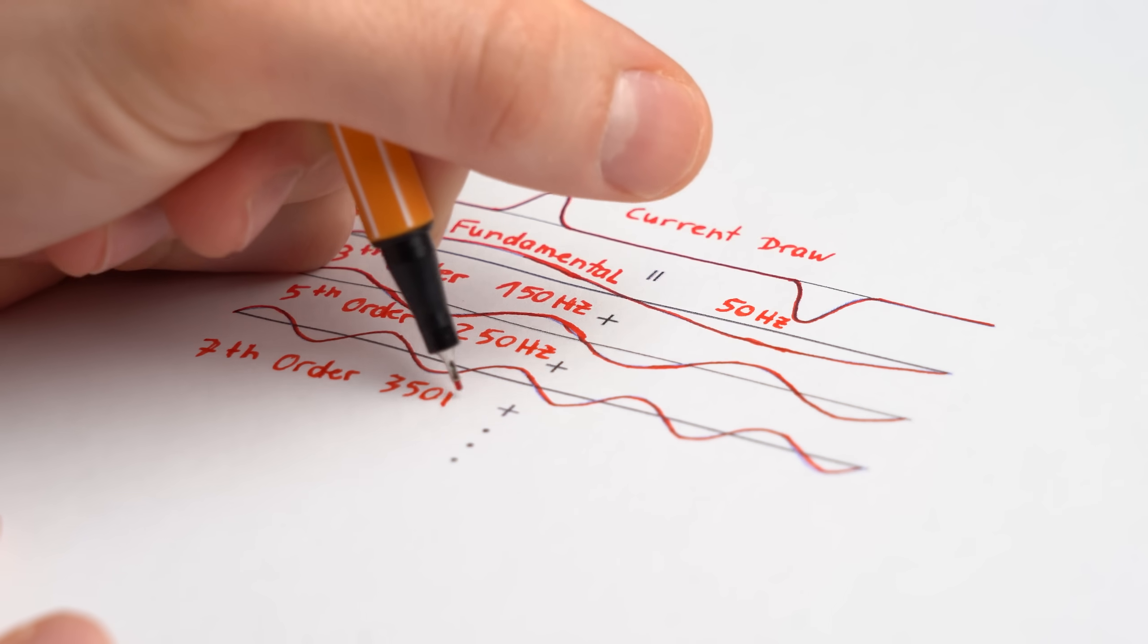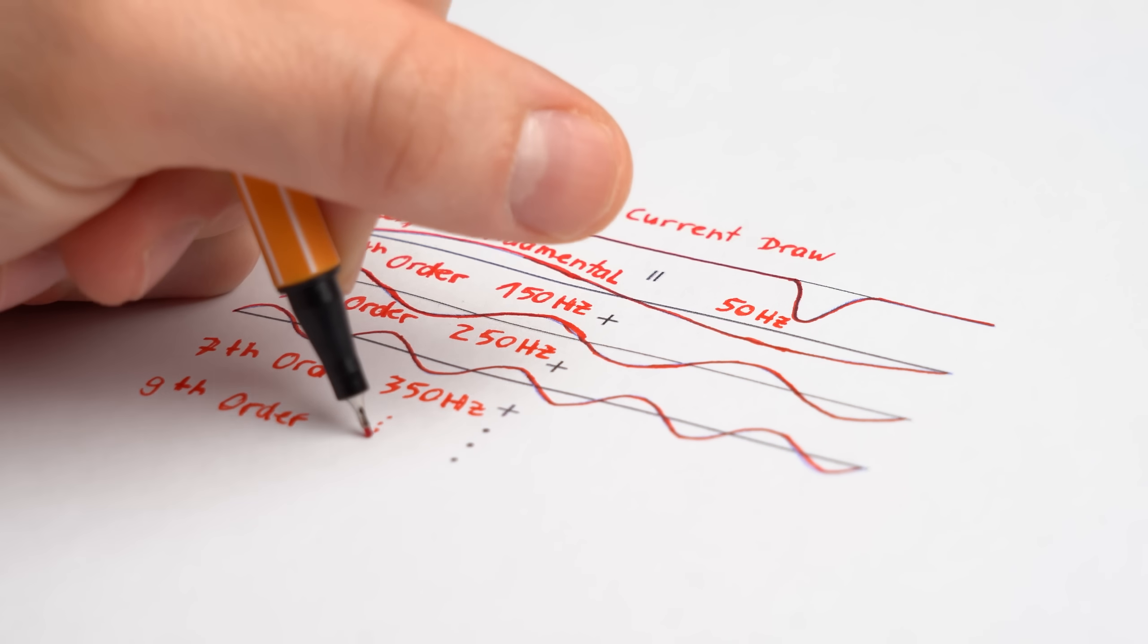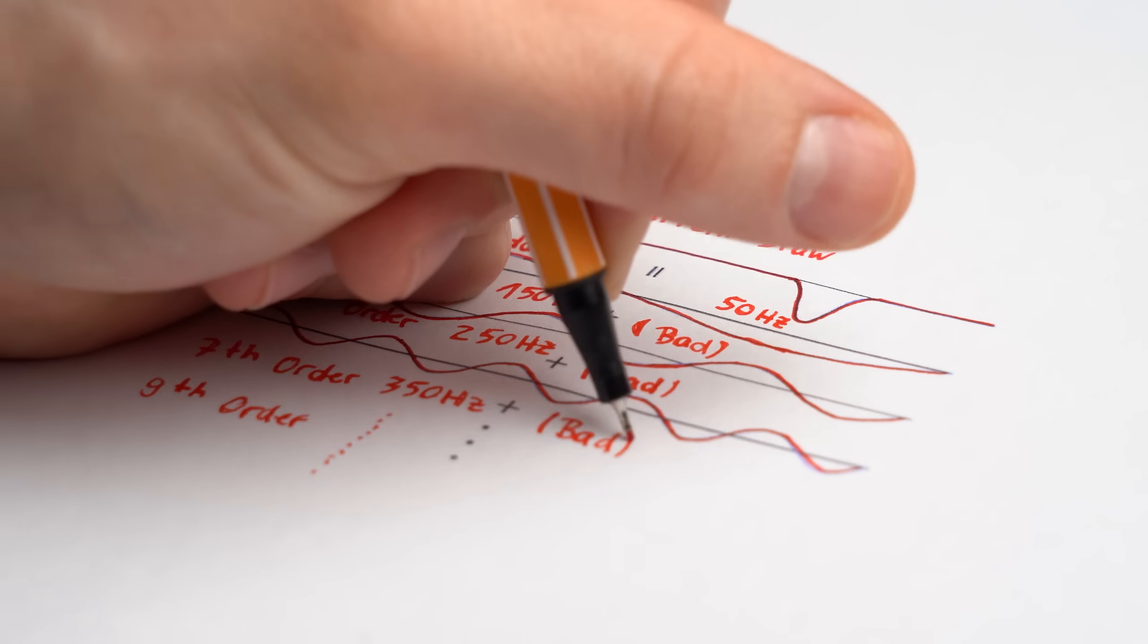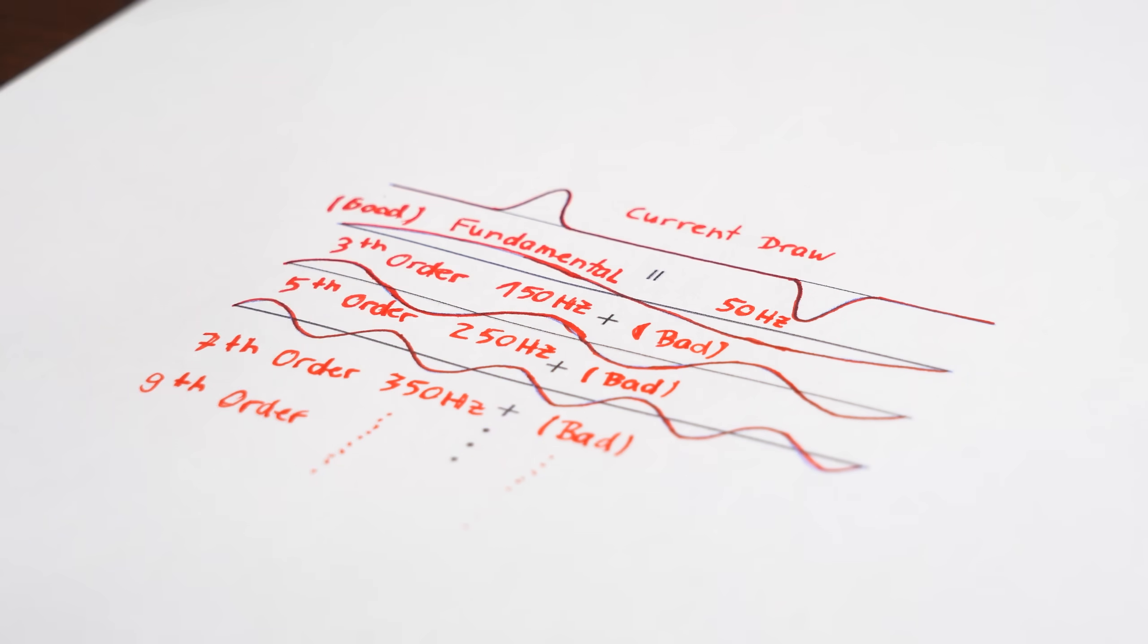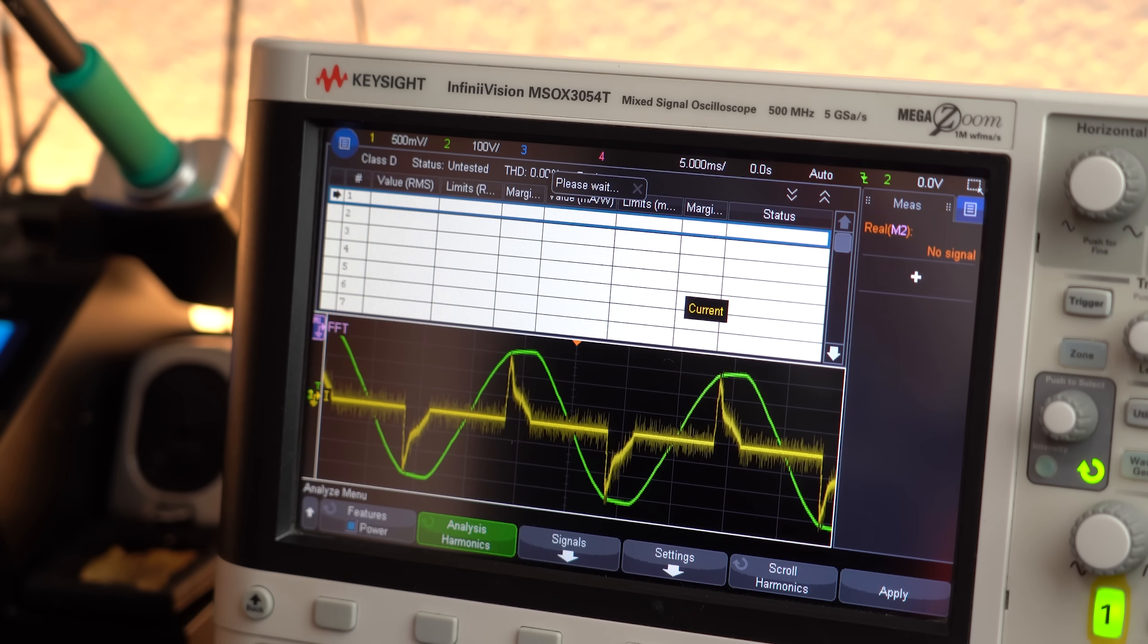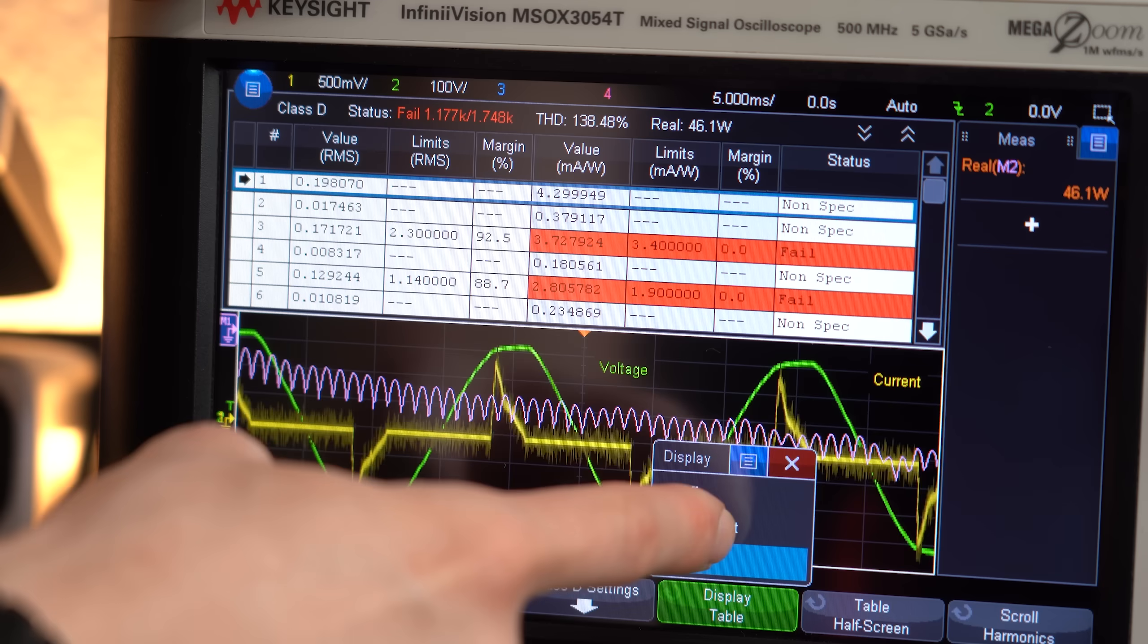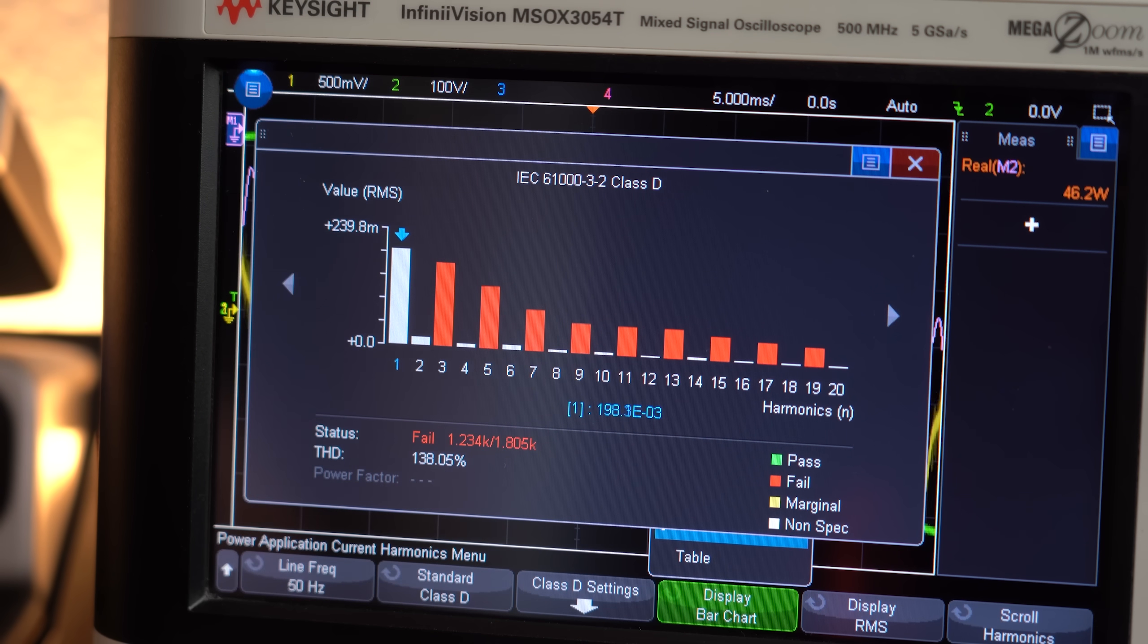And they do kind of feature a phase shift that creates the reactive power. By using my oscilloscope we can actually see how much they matter in comparison to the fundamental 50Hz frequency. And let's just say that they are pretty dominant on the screen here.